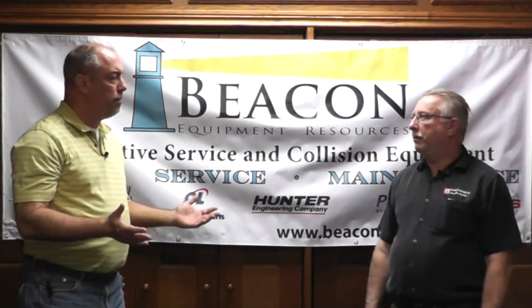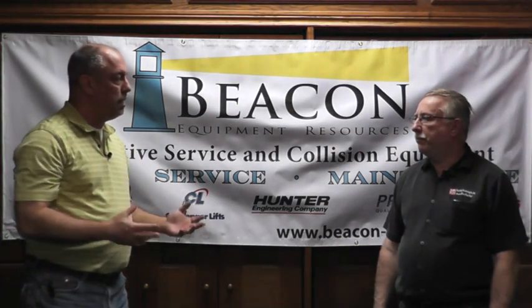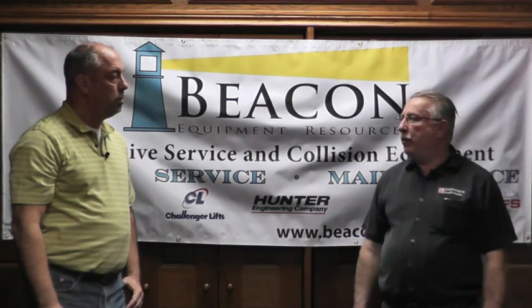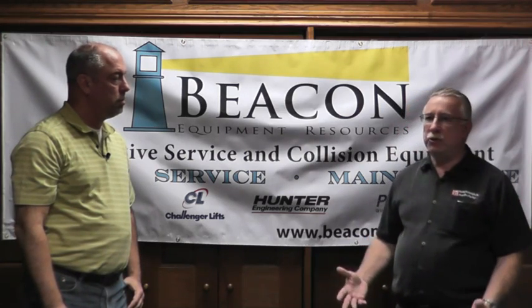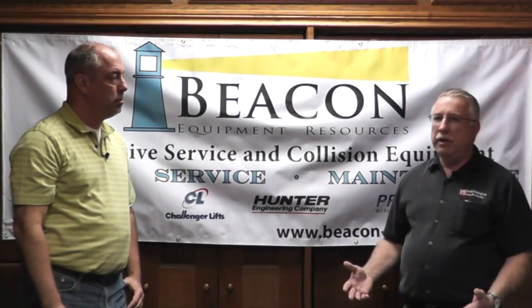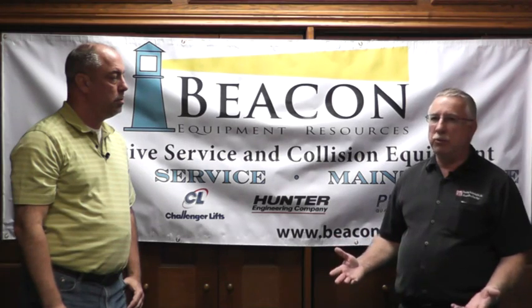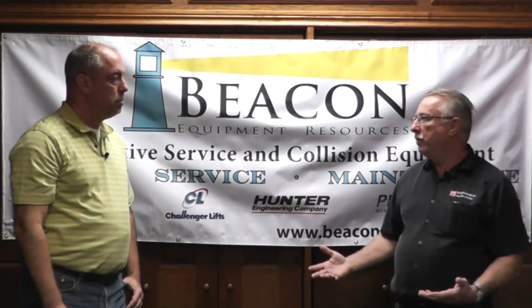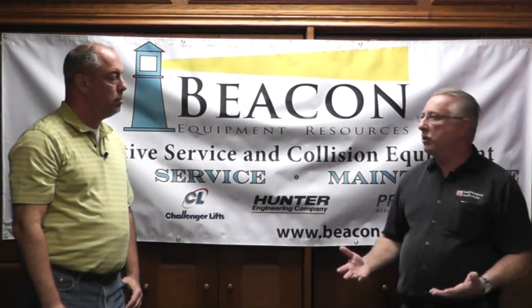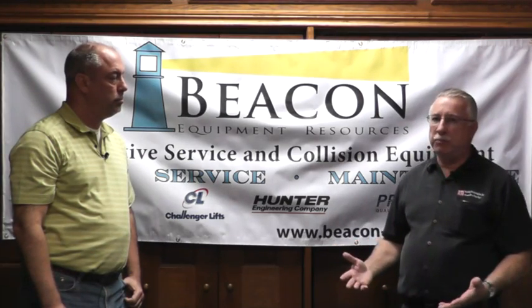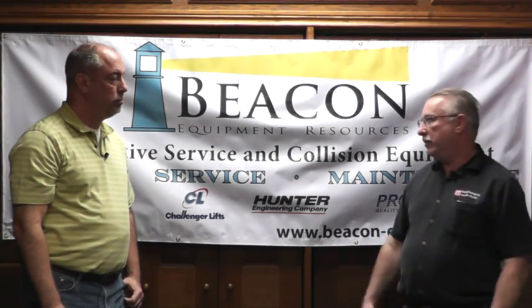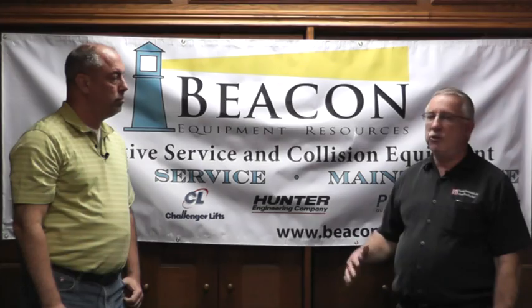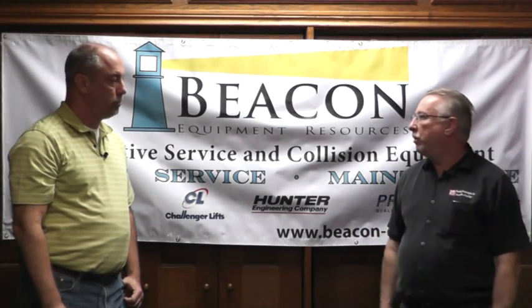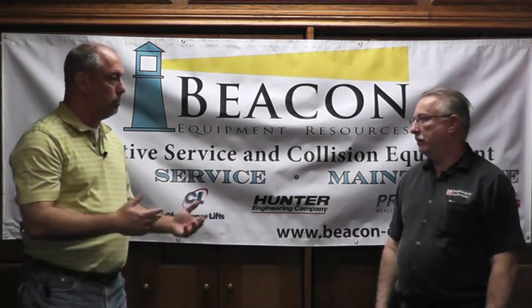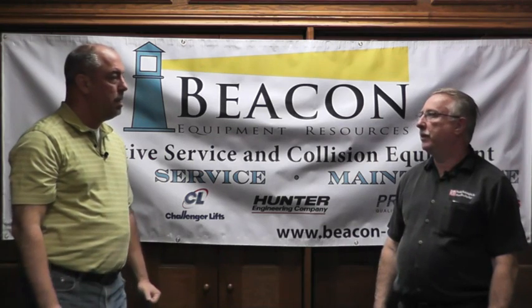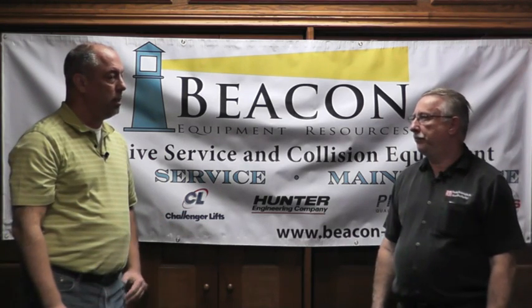Al, let's talk about oil first. Where does oil come from in the airlines? Oil is a byproduct of the compressor. As the compressor runs, it uses oil, and all compressors, whether they're a hydrovane or a piston or a screw, always have a little bit of oil coming down line. The newer the compressor, the less profound the problem. But as compressors get older, they throw more oil down line. The seals loosen up, and it bypasses more, just like a car. It will bypass more oil, and it gets downstream into the lines.